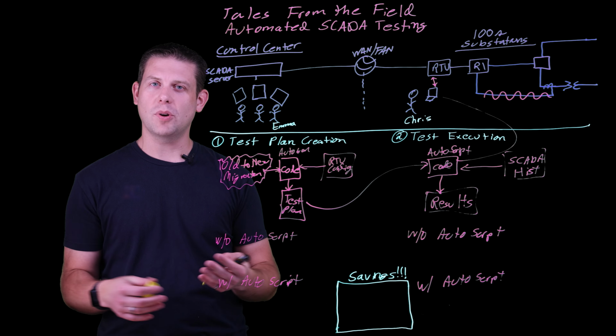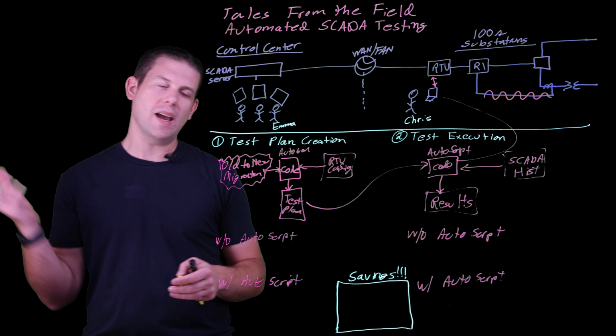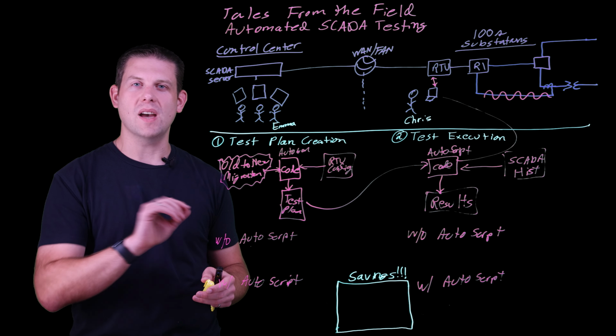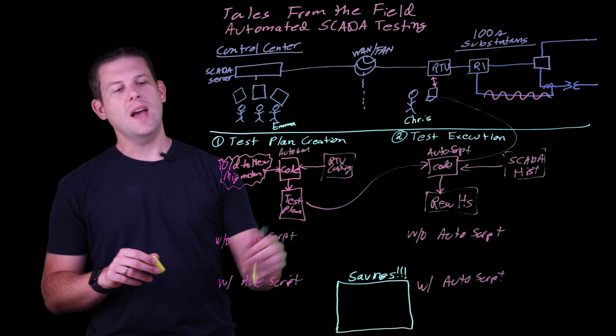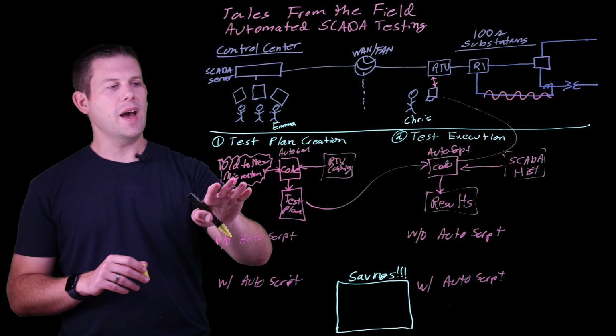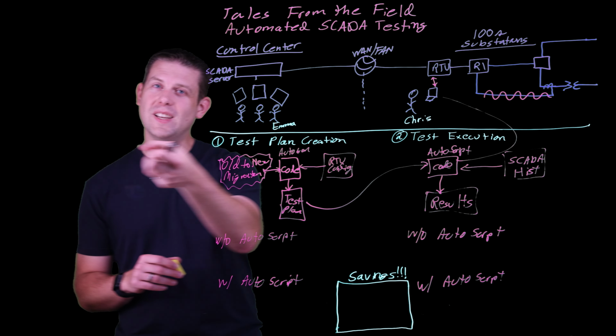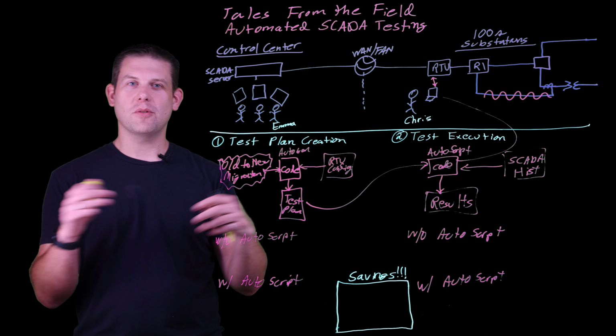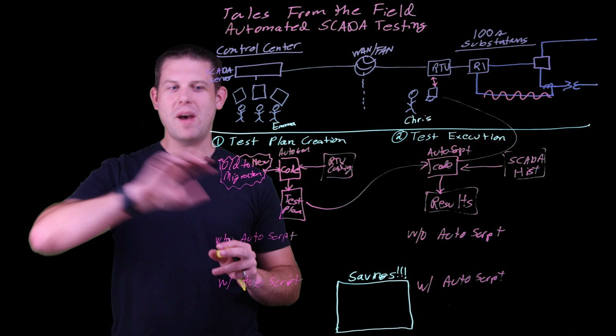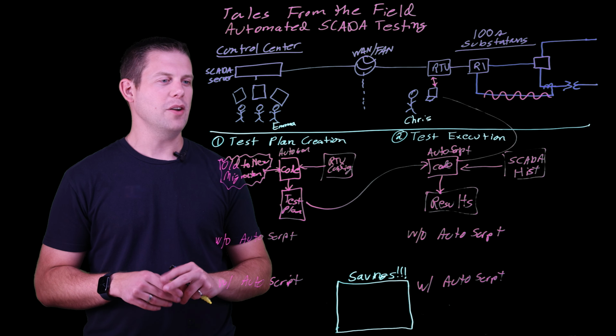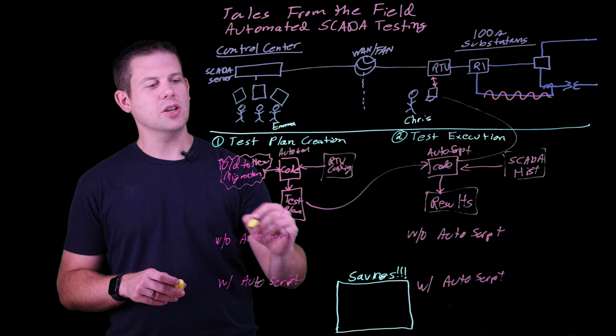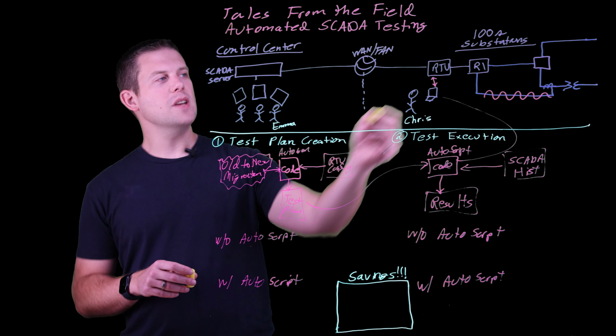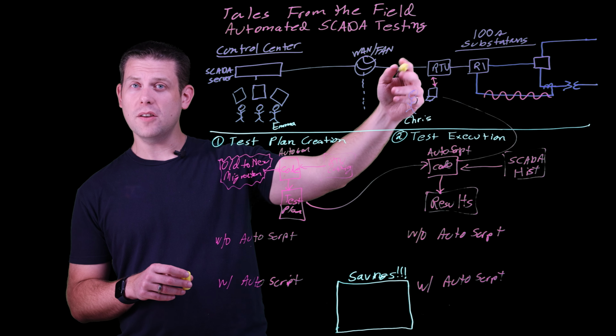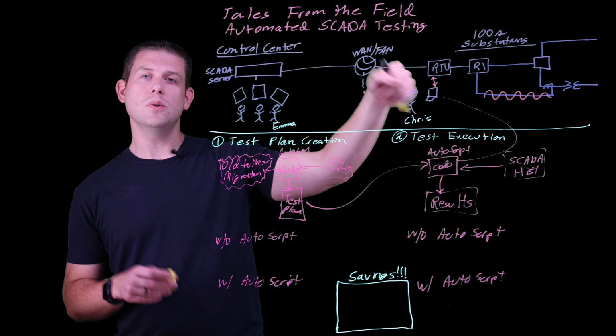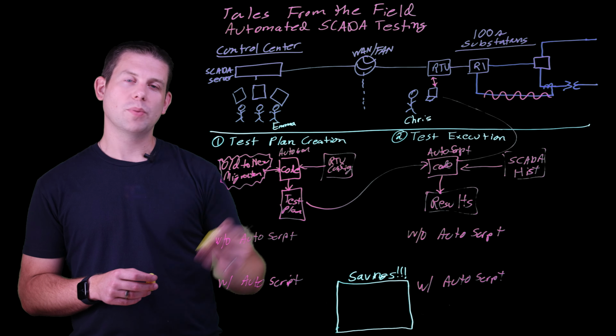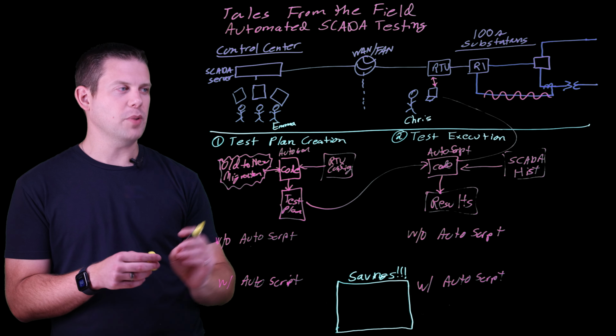The test plan was able to take in the migration files from this SCADA upgrade, moving from a legacy SCADA system to a brand new ADMS, Advanced Distribution Management System. We wrote software capable of digesting the migration file, and because of this we were able to find tons of errors and send them back to the migration team to help solve. This AutoGen code also took in the RTU config file for the station's remote terminal unit, and produced the station-specific test plan.